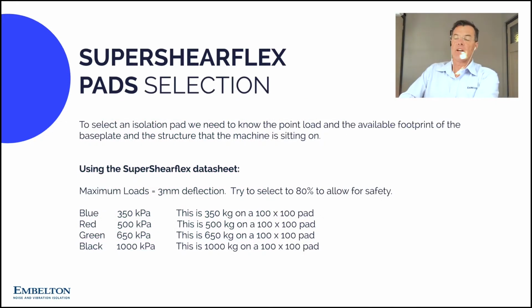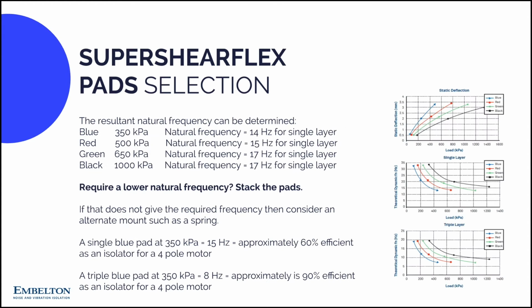Super shear flex pad selection. We use the machine weight and the available pad footprint to select the super shear flex pad. We want it to deflect, so we have various grades available to achieve that. A 100 by 100 blue pad will take 350 kilograms, while a red will take 500, green 650 and black 1,000 kilograms. The deflection of the pad results in a natural frequency.